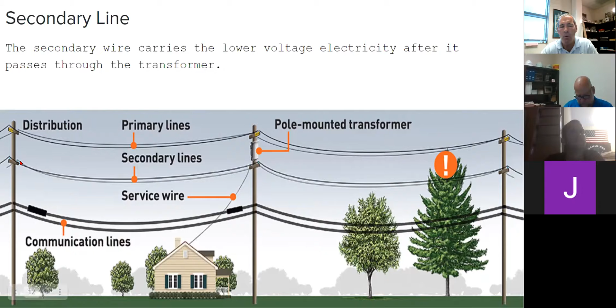When I have a service line, that's actually going to the consumer - still secondary voltage. For example, I've got a transformer down here, I come with a line to this pole - that's my secondary line, 120, 240. As soon as I come off that secondary line and go to the house, that's my service line, still 120, 240. The industry differentiates between the two, just so you know. That's the line that feeds the house, that's service line; the line that feeds from pole to pole, that's secondary - but they're all still at the same voltage.